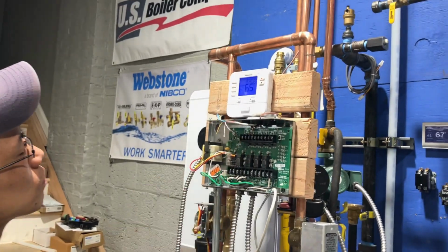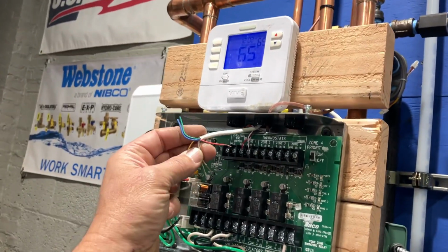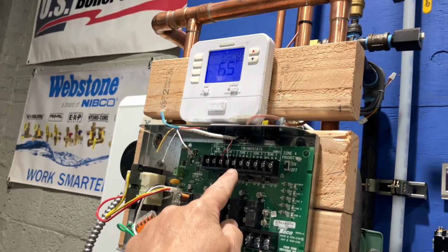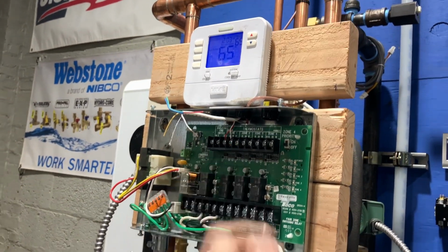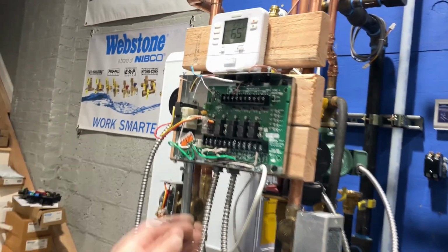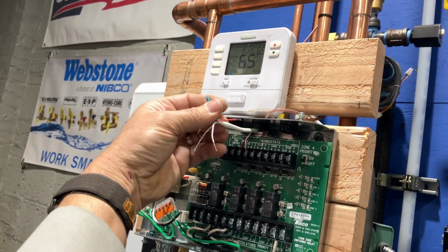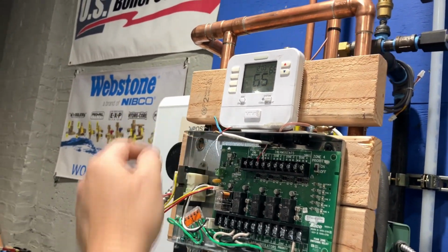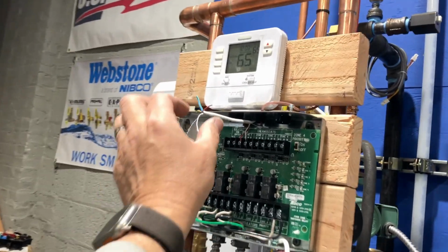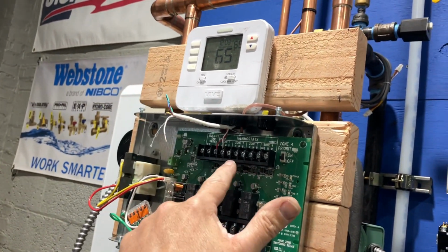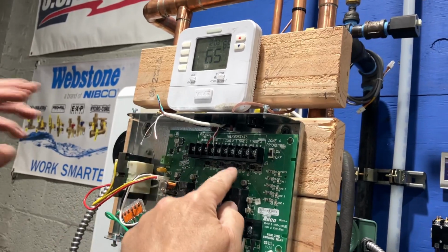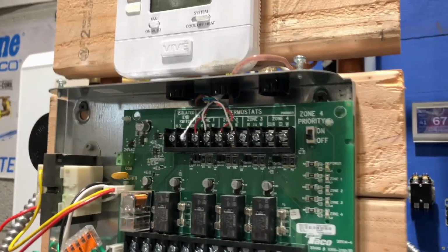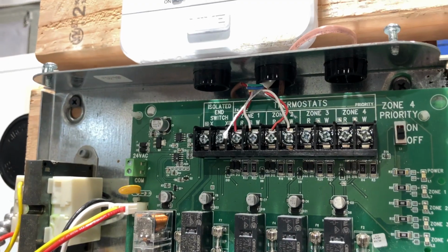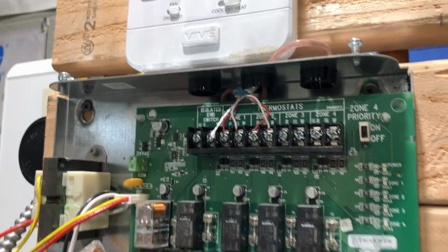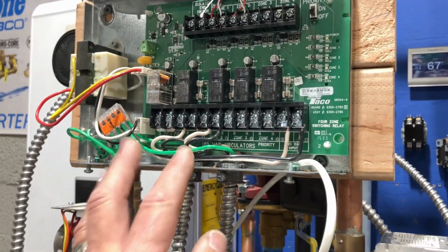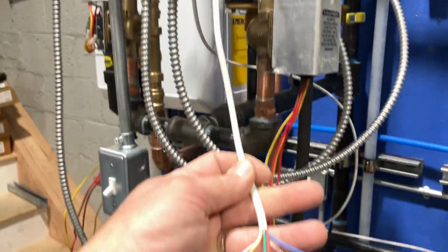Perfect. Now, these two wires need to go on the two terminals on our switching relay. Remember, we're not using any of the other two wires for this, so we can cut away those extra wires. Then the red wire is going to go on zone 2 for R, and the white wire is going to go on zone 2 W. All right, so we have our red and our white wire hooked up to zone 2. Everything else here is connected with the exception of this wire here.